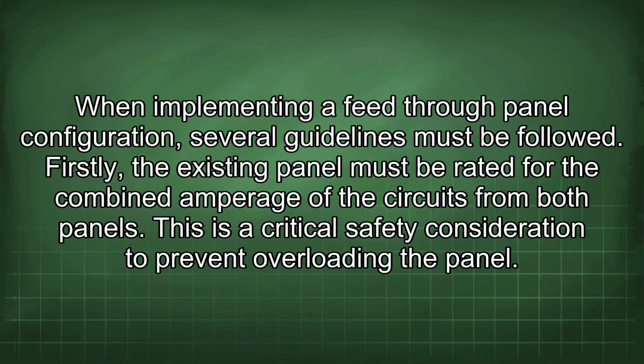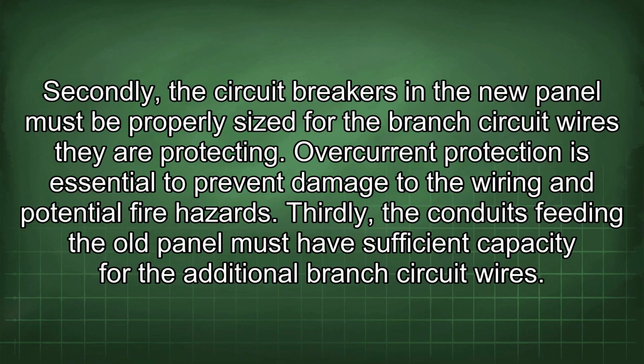When implementing a feed-through panel configuration, several guidelines must be followed. Firstly, the existing panel must be rated for the combined amperage of the circuits from both panels. This is a critical safety consideration to prevent overloading the panel. Secondly, the circuit breakers in the new panel must be properly sized for the branch circuit wires they are protecting. Overcurrent protection is essential to prevent damage to the wiring and potential fire hazards.